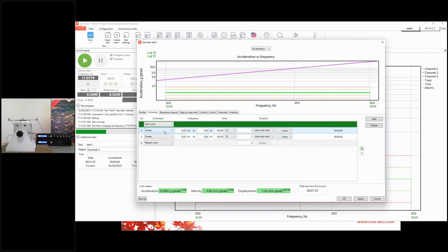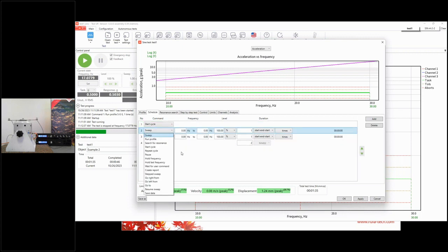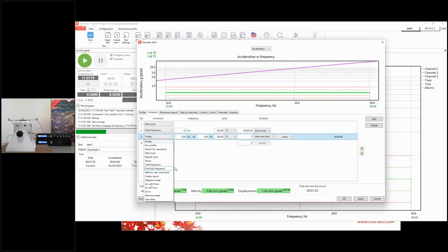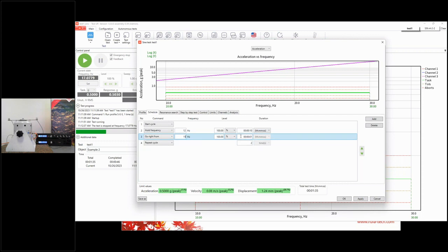Sometimes you need to generate exact frequencies during a test for research purposes. For this we have a command called Hold Frequency. You enter the desired frequency value, the level in your preferred units, and the duration. Since we found a resonance at 12 Hz, we enter that frequency and hold it for 10 seconds. After that we want to sweep starting from 15 Hz.